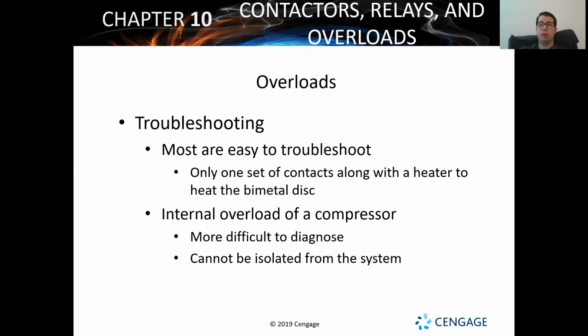Now, what they want to hear is when you go out that first day, well, the overload seems to have tripped. This is usually caused by something going wrong with a motor. I'm going to check out the health of your motor and see if I can find anything that looks suspicious. So I'm going to check capacitors.